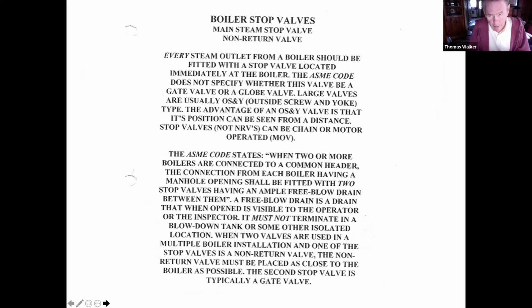The other valve they love to talk about are boiler stop valves, sometimes called main steam stop valves. Every boiler should have one, all right? But the big question they're going to ask you is, when do you need more than one? Boilers connected to a common header with other boilers that have manholes are required to have two stop valves. It's the only provision in the ASME code that allows for personal protection. In other words, you can get in that boiler with other boilers operating attached to that header.